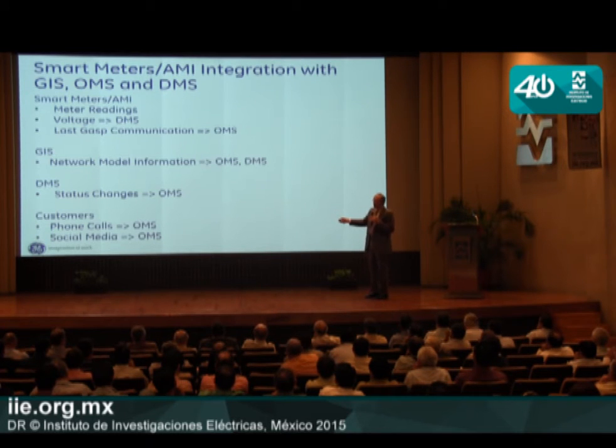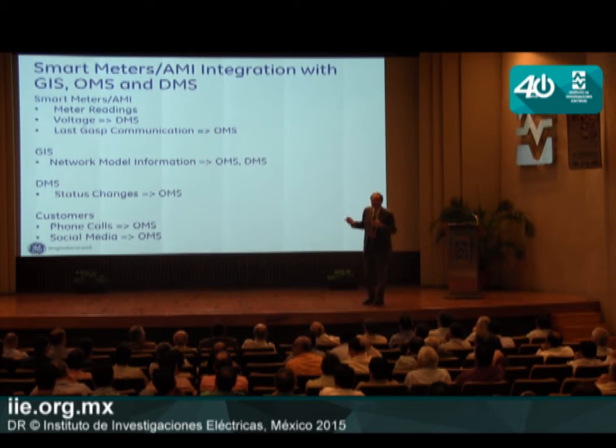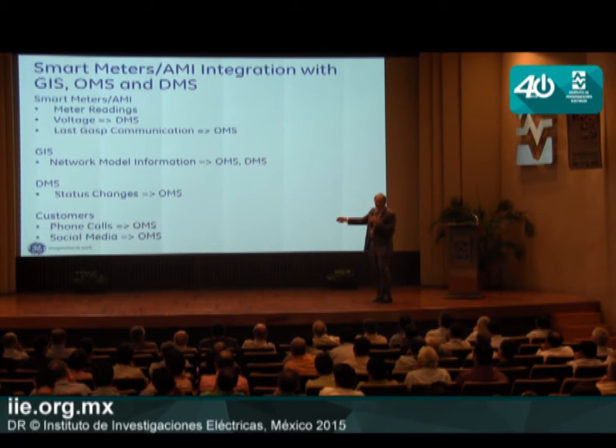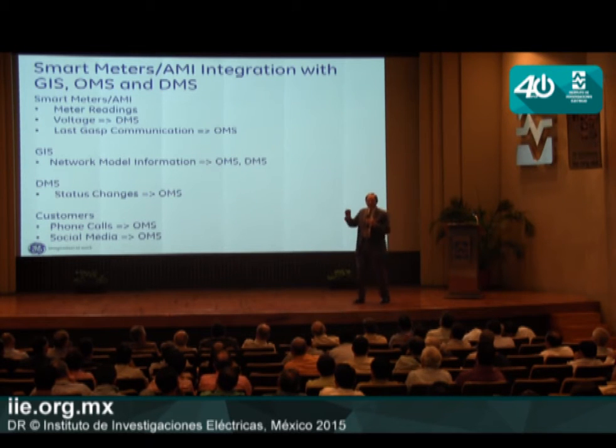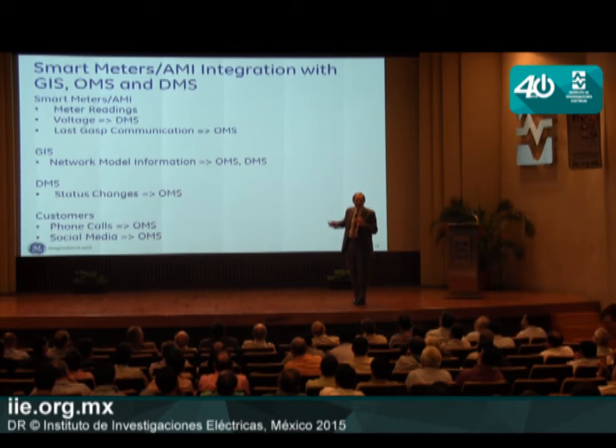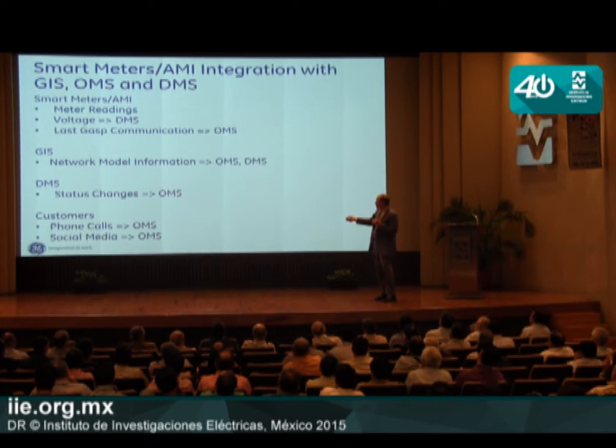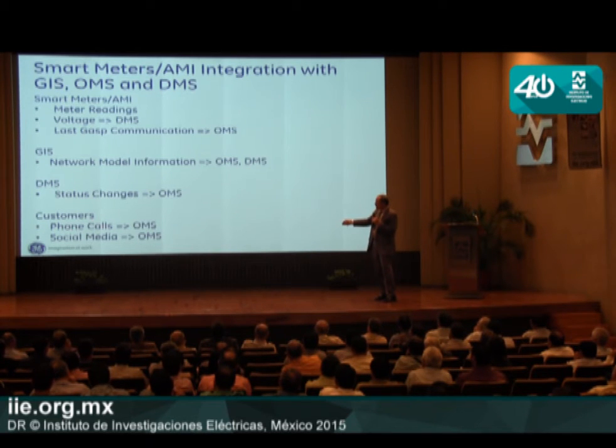We keep the GIS up to date. Another key link is the distribution management system with the outage management. In a SCADA system, when a status change occurs, like a breaker trips, we know about it typically within 2 seconds. So let's say a distribution feeder breaker trips. We send that status change to the outage management system, which has the network model. So once the OMS knows that a feeder is de-energized, it knows exactly which customers are fed from that feeder. It knows all these customers now have an outage, and the time it occurred, from one status change. Customers typically rely on phone calls to the utility to report they're without power.